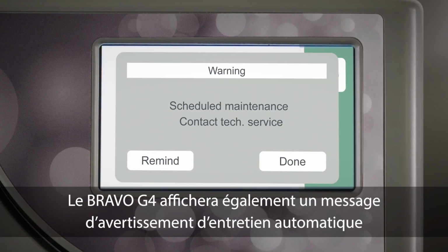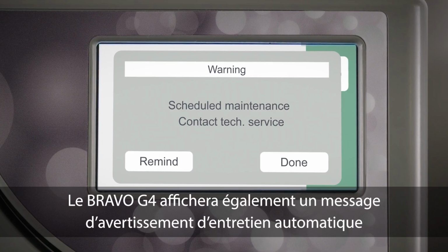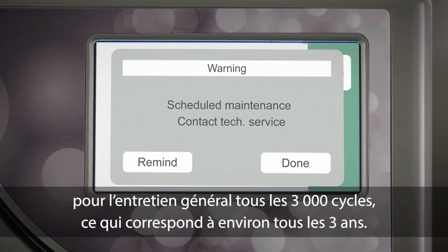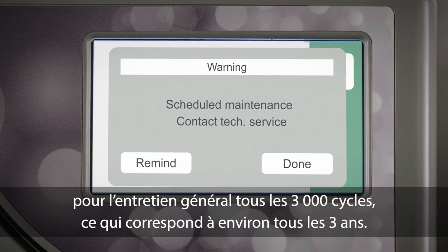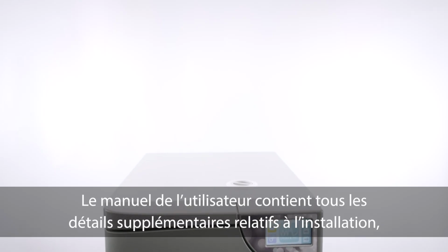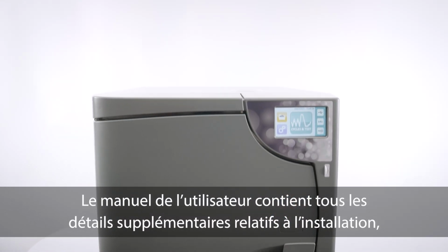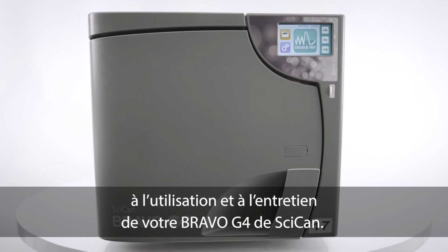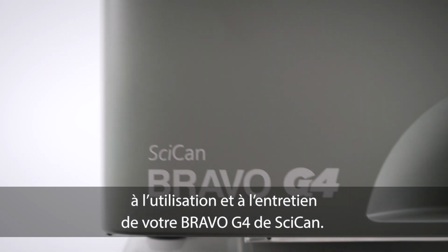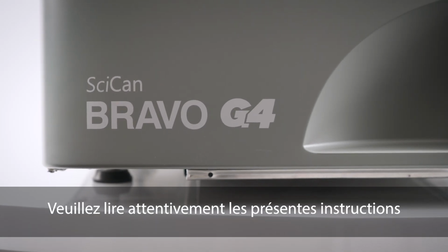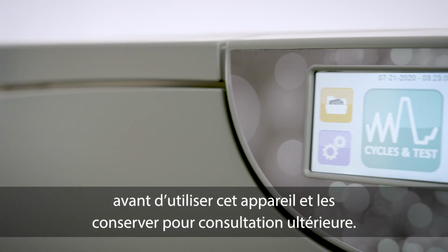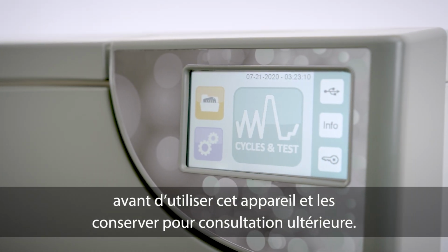The Bravo G4 will also display an automatic maintenance warning message for general service every 3,000 cycles, which is roughly every 3 years. Additional details about installing, operating, and maintaining your SciCan Bravo G4 are all contained within the operator's manual. Please read these instructions before operating this unit and keep them for future reference.